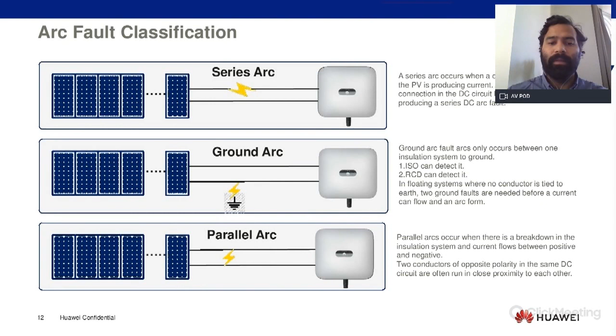In the case of a PV string, between the positive and the negative, this can occur because, as you know, sometimes the positive and the negative wires run very close and parallel to each other, for example on ground-mounted systems, and also on rooftop applications. However, the chance that a breakage or crack in the insulation happens at the same point is very unlikely. So this situation is not very common on PV systems. As I was saying before, the standards are focused mainly on series arc because this is the one that occurs the most.